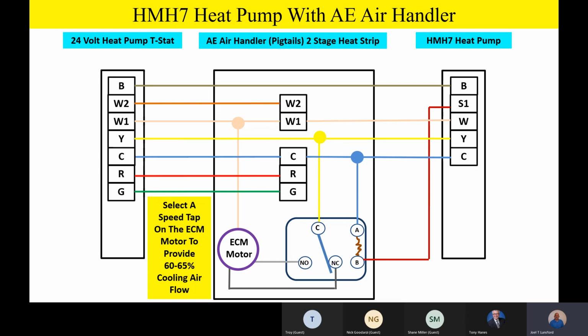Well, team, get as close as you can to about 60%. 60 to 65% is the range. But if you were to squeeze down to 58% or 55%, or squeeze up to 68% airflow, you get the idea. Try to stay around 60% airflow on that low airflow, because if you're around 60% airflow and the outdoor unit commands to reduce airflow, we'll show you how to do that here in a minute with the S1 input from the outdoor unit. But if we're around 60% airflow, we'll have nice humidity control. And as the outdoor unit modulates down and we have reduced capacity, we're going to match or closely match that reduced capacity with less airflow inside.